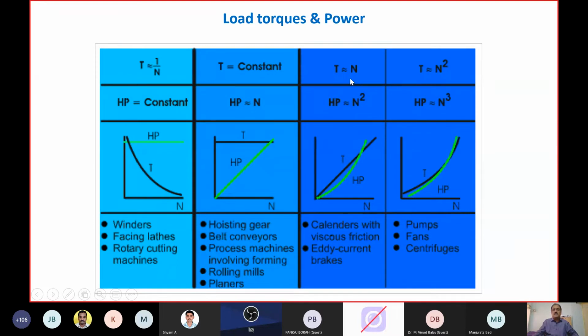Torque proportional to speed is another area, where power becomes proportional to the square of the speed. Calenders and eddy current drives are examples of this. Torque proportional to the square of the speed, which is pumps, fans and centrifugal compressors, gives rise to power proportional to the cube of the speed. So when it comes to using a VFD for speed variations to optimize the load torque required by the machine, substantial, cube-times energy saving is available by using a VFD. And therefore, for any pump, fan or centrifuge application, a VFD is an excellent choice for energy conservation, the 2-digit energy saving which we discussed.